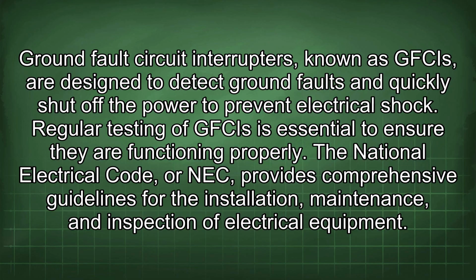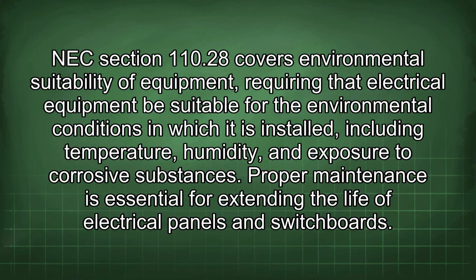The National Electrical Code, or NEC, provides comprehensive guidelines for the installation, maintenance, and inspection of electrical equipment. NEC Section 110.28 covers environmental suitability of equipment, requiring that electrical equipment be suitable for the environmental conditions in which it is installed, including temperature, humidity, and exposure to corrosive substances. Proper maintenance is essential for extending the life of electrical panels and switchboards.